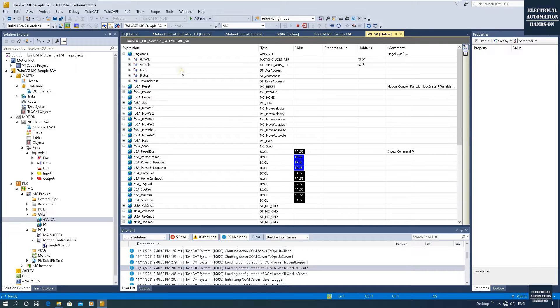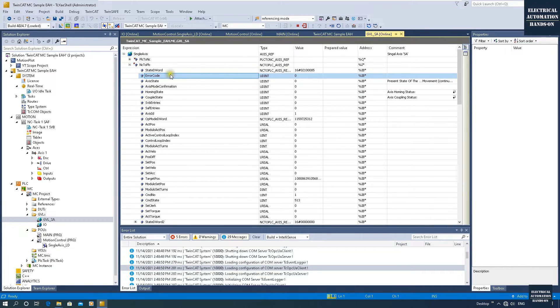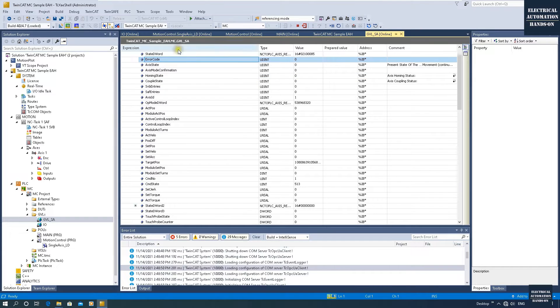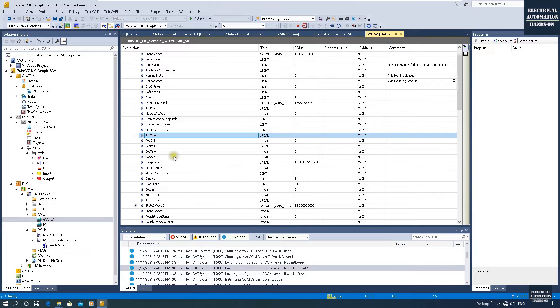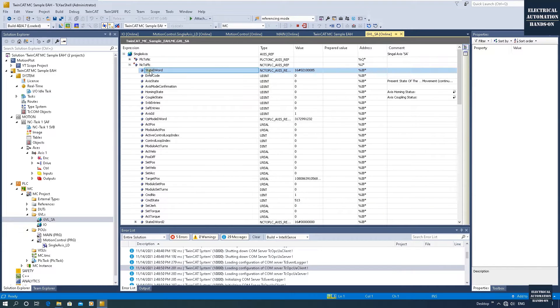To check the detail status, there are basically two places we can look. One is the NC to PLC section here, where we can see the StateDWORD. This StateDWORD is very important information for the drive and for this axis. Also there is the error code — keep in mind the error code showing here is a UDINT, an integer value. And there are also a couple of status values: the actual position, actual velocity, and actual torque, which are all important values from the axis.